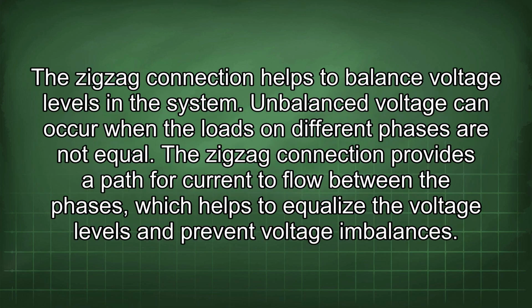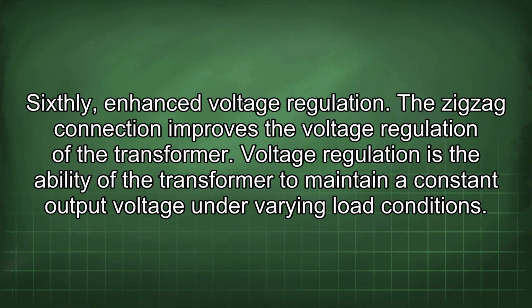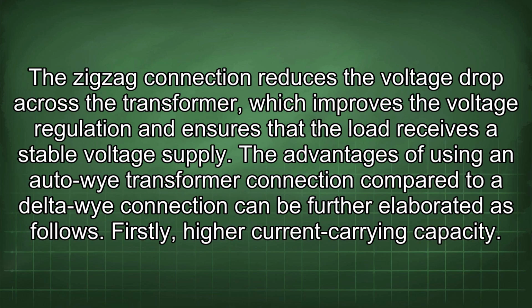Fifthly, balanced voltage support. The zigzag connection helps to balance voltage levels in the system. A voltage imbalance can occur when the loads on different phases are not equal. The zigzag connection provides a path for current to flow between the phases, which helps to equalize the voltage levels and prevent voltage imbalances. Sixthly, enhanced voltage regulation. The zigzag connection improves the voltage regulation of the transformer. Voltage regulation is the ability of the transformer to maintain a constant output voltage under varying load conditions. The zigzag connection reduces the voltage drop across the transformer, which improves the voltage regulation and ensures that the load receives a stable voltage supply.